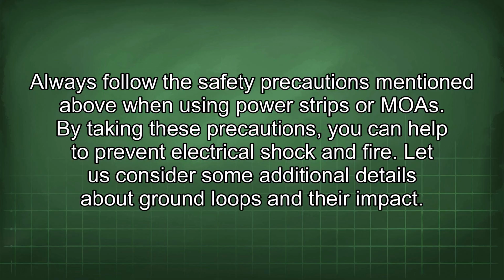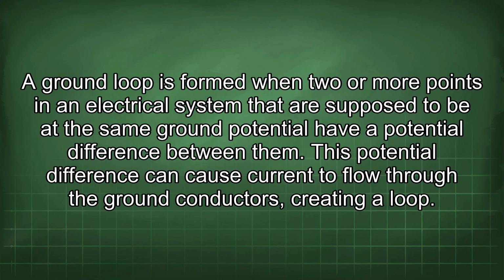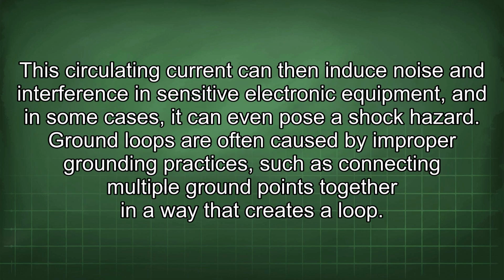Let us consider some additional details about ground loops and their impact. A ground loop is formed when two or more points in an electrical system that are supposed to be at the same ground potential have a potential difference between them. This potential difference can cause current to flow through the ground conductors, creating a loop. This circulating current can then induce noise and interference in sensitive electronic equipment, and in some cases, it can even pose a shock hazard. Ground loops are often caused by improper grounding practices, such as connecting multiple ground points together in a way that creates a loop.